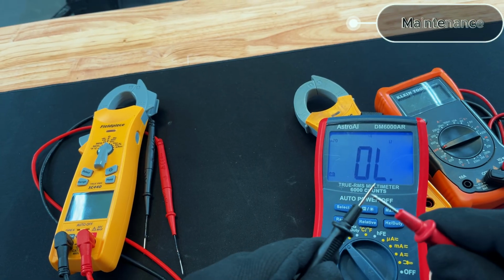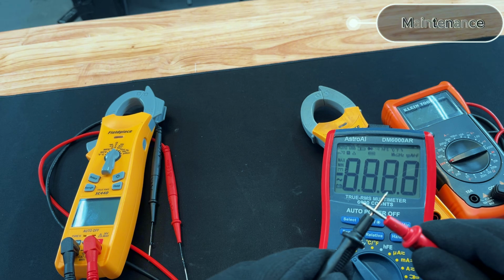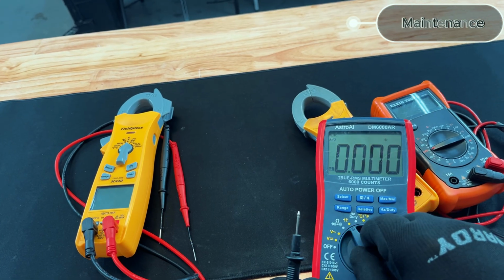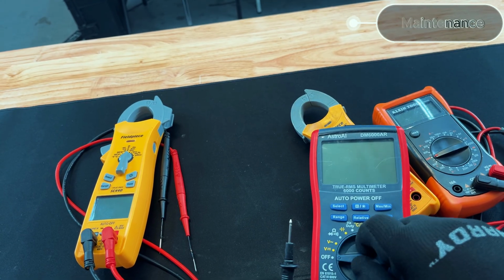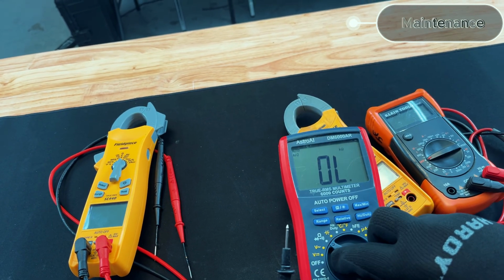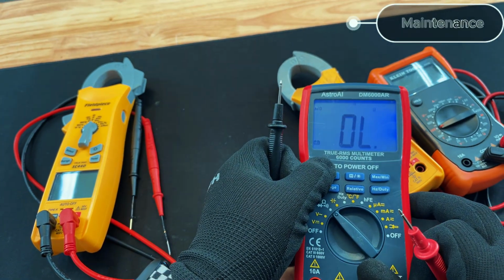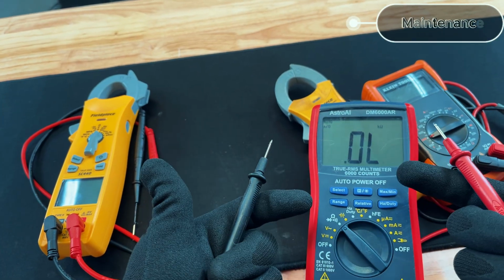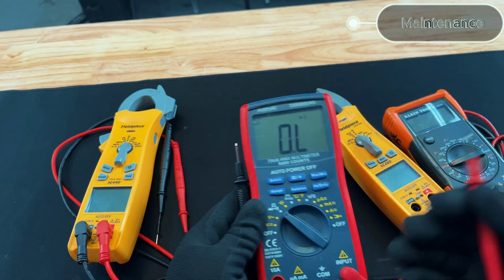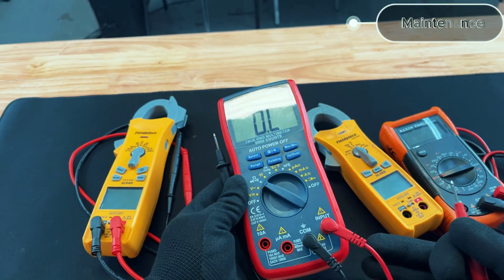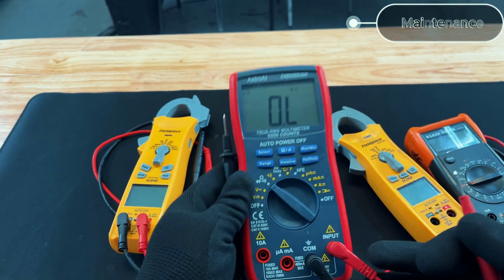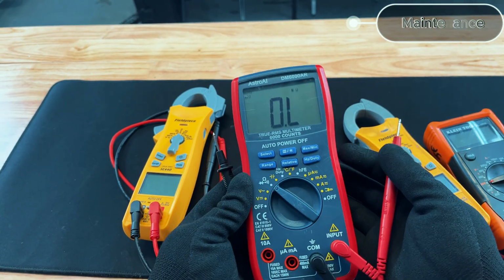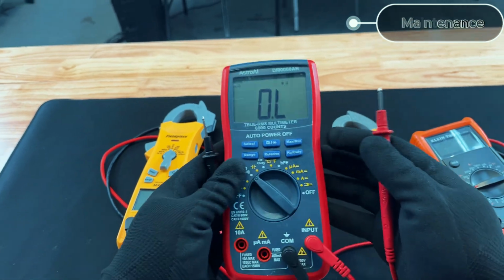I have it on a continuity check, and let's check continuity. As you can see, it kind of just shut off and turned back on. If I go through the settings, it could also cause it to shut off and turn back on. Again, let's put it on continuity, so it's even kind of blinking a little bit, and checking continuity, meter resets. So that's a good way to know, okay, my battery's the problem. And this is not going to be a meter you want to be using, because you might have some odd readings that are going to make you go down rabbit holes that are issues that are not true. So make sure that you are checking your meters and check your batteries.